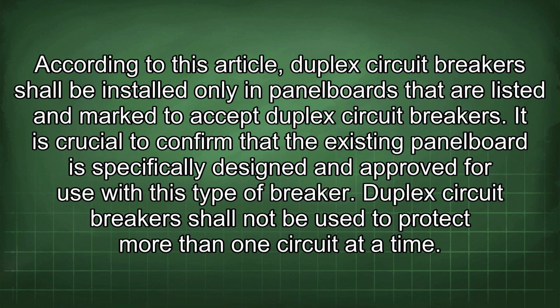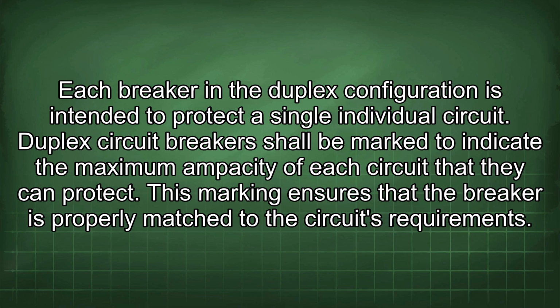According to this article, duplex circuit breakers shall be installed only in panel boards that are listed and marked to accept duplex circuit breakers. It is crucial to confirm that the existing panel board is specifically designed and approved for use with this type of breaker. Duplex circuit breakers shall not be used to protect more than one circuit at a time. Each breaker in the duplex configuration is intended to protect a single individual circuit.